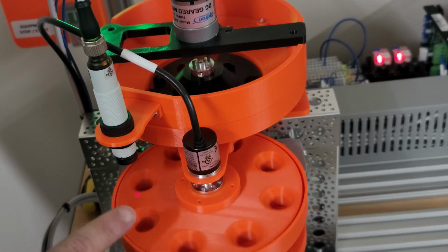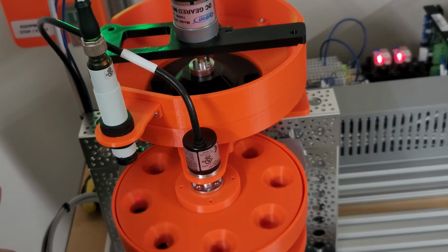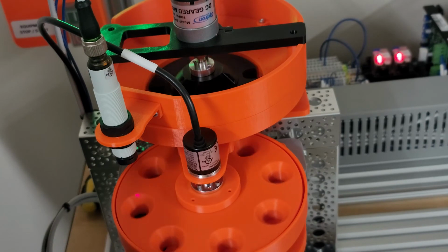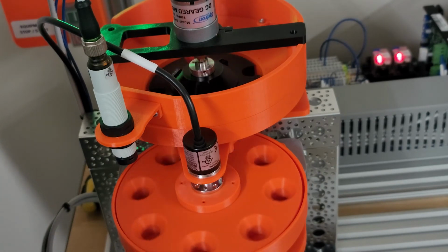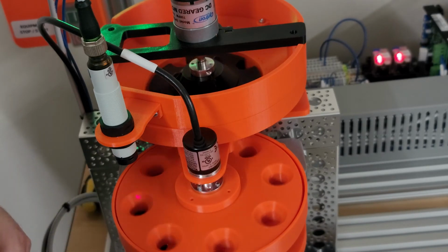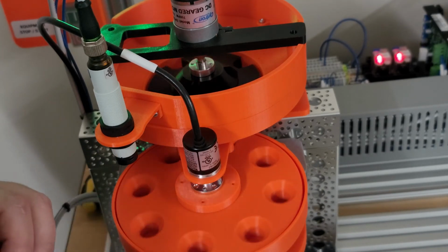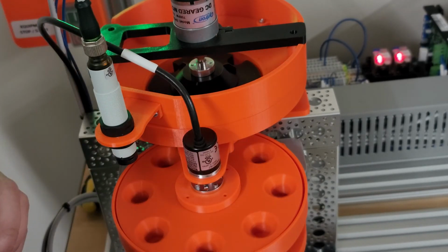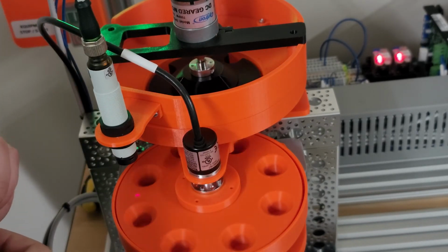I think what's happening is that the table is turning a little bit too fast. So sometimes if the marbles aren't quite where they need to be, the marbles won't fall into the chute. So what we'll probably need to do is slow the turntable down just a tiny bit so that it has a little bit more time to catch up to the in-feed indexer.